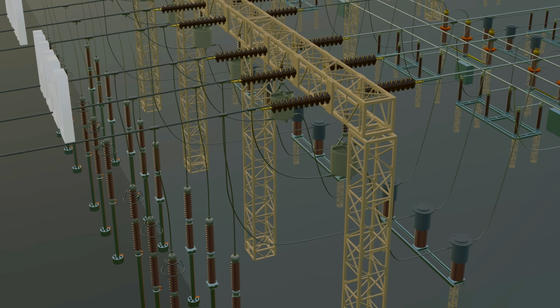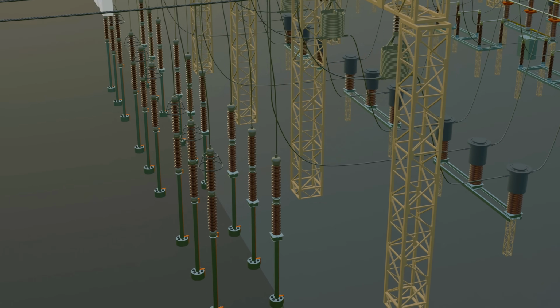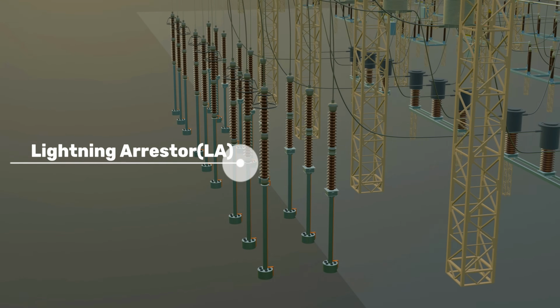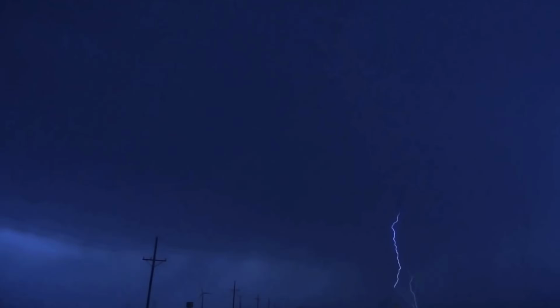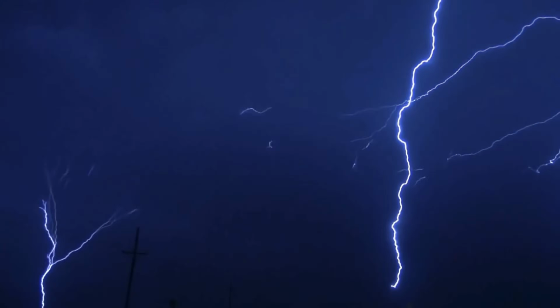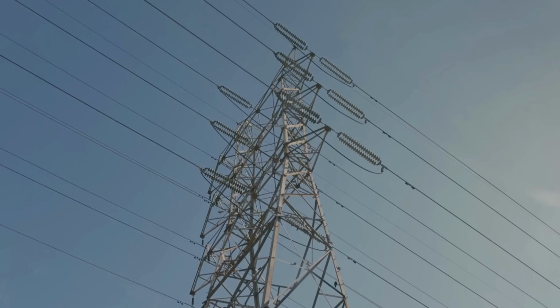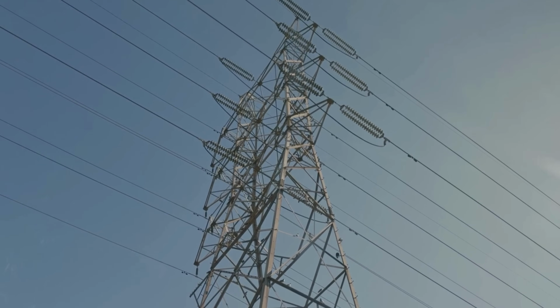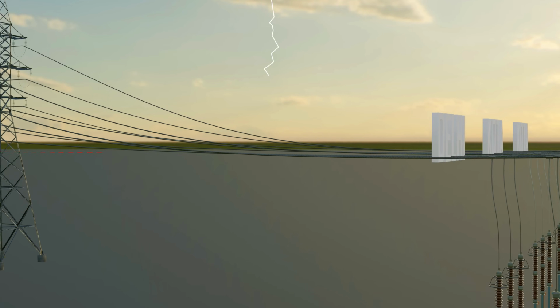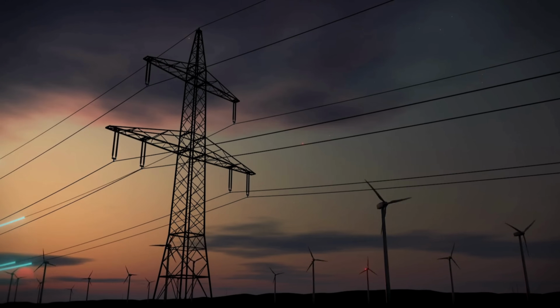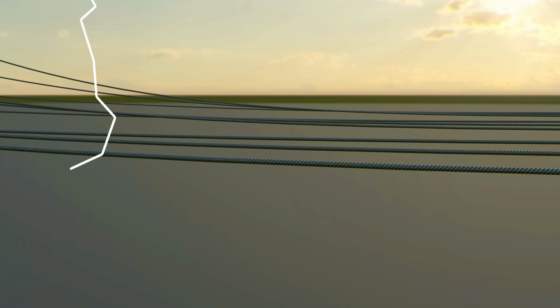The first equipment they connect to in the switchyard is a lightning arrestor, installed in parallel with the line. During thunderstorms, lightning often splits into multiple branches as it nears the ground. These branches naturally target the tallest objects, usually trees, buildings, or transmission lines. As transmission lines are installed at great heights, they're highly prone to lightning strikes. A line carrying 4 lakh volts can suddenly face a surge of 1 to 5 million volts, far beyond the insulation and design limits of substation equipment.